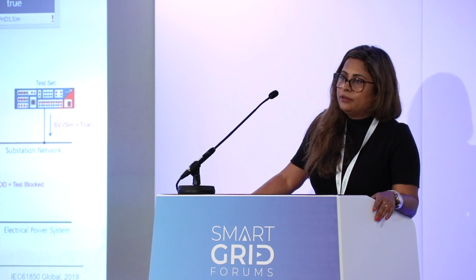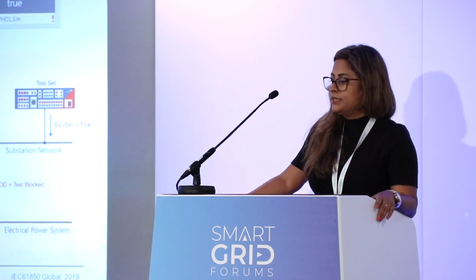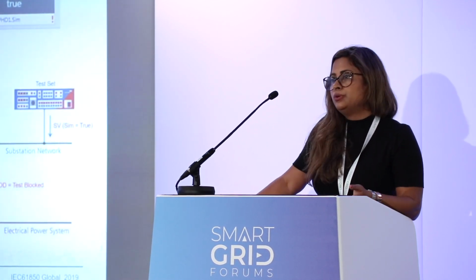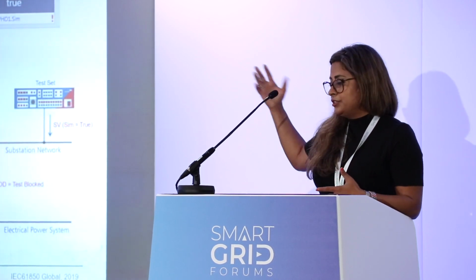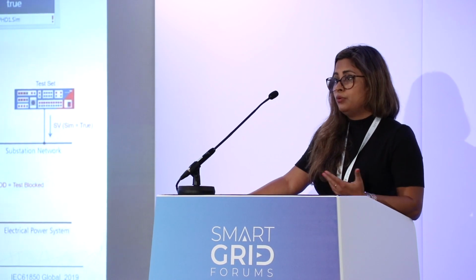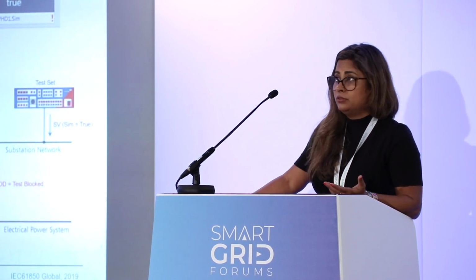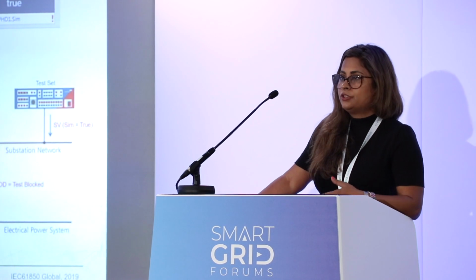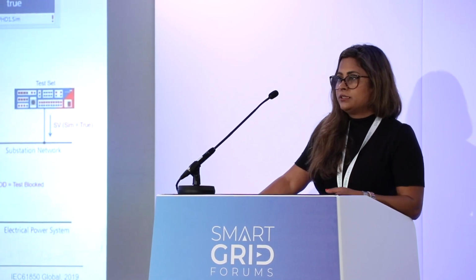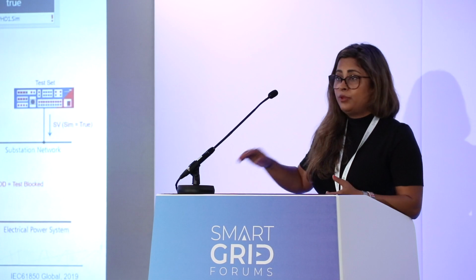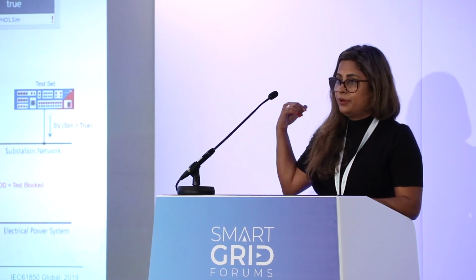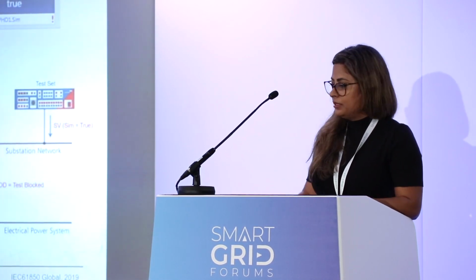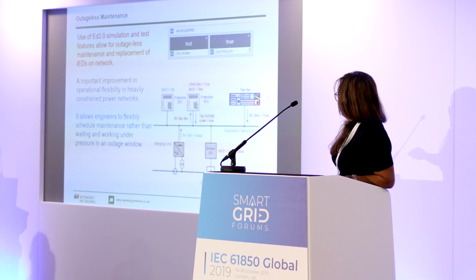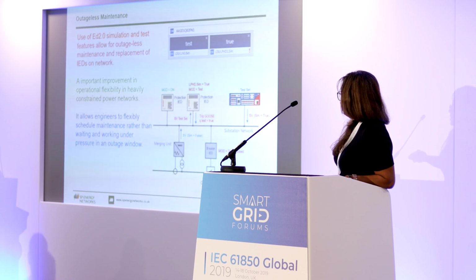So how can outage-less maintenance help there? In addition to feature-based maintenance regimes, transmission protection systems generally have a main 1, a main 2, and in some cases a backup. So you can pretty much take one of the systems out of service without touching anything, putting the right flags on it. You put a test set and simulate whatever faults you need to test.